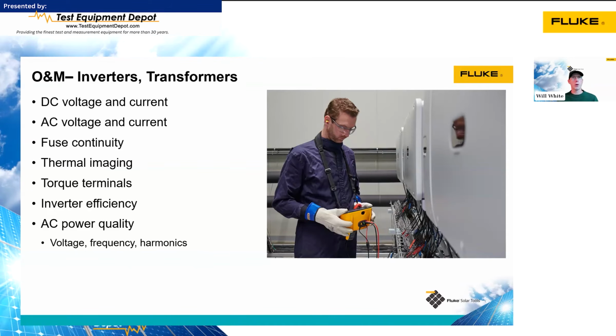We can also check our inverter efficiency and then do AC power quality measurements, things like measuring our voltage, our frequency, looking for harmonics. We can also look for transient voltage spikes with those higher end power quality meters. Now, I'll just say on this slide here, this is a picture from Europe. This, I believe, is actually the PV array that is installed on our European headquarters in Eindhoven in the Netherlands. That's why you see the single conductors coming out of the bottom of the inverter. That's typically how they do it in Europe. They don't use conduit as much as we do here in the US.